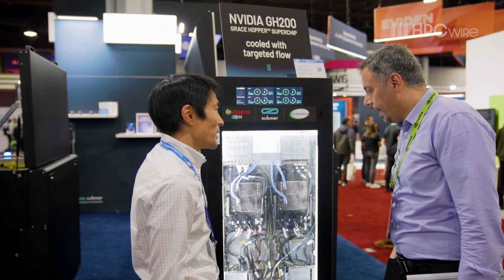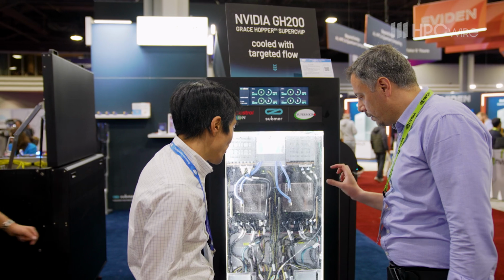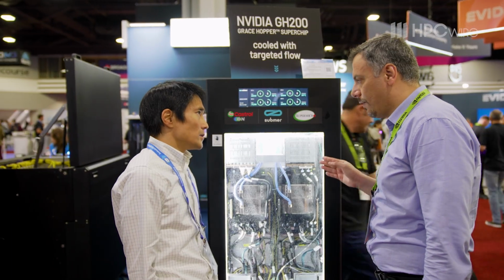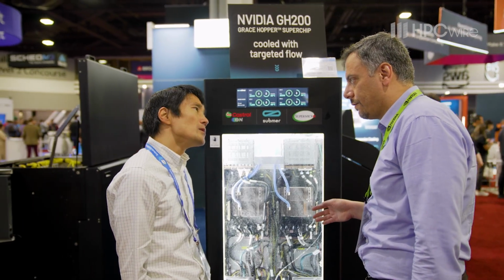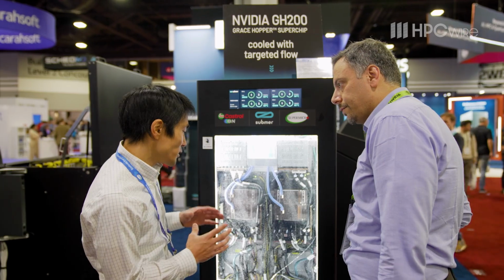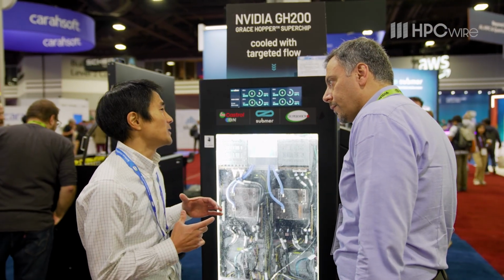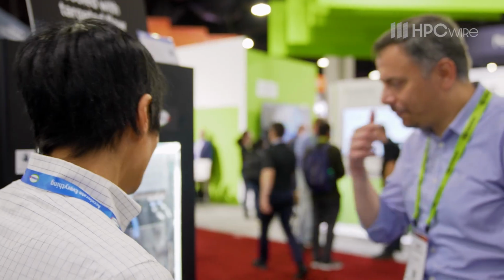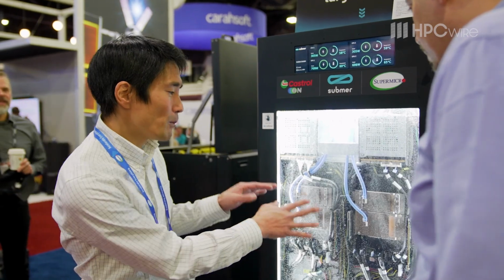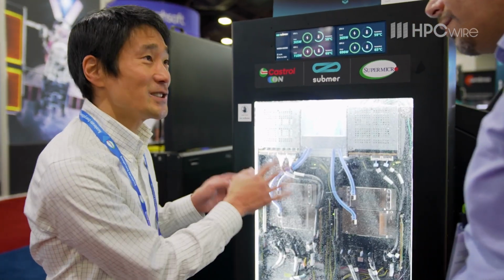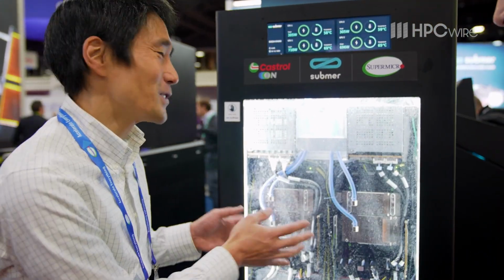With immersion cooling, it's not that way. There is no air cooling component. It's just one loop, and the power required for cooling is just the power required to power a couple of pumps and a couple of fans. That's how you get down to a PUE of 1.02. So with immersion cooling, you get the best of both worlds: high performance cooling, but you're saving a lot of money and energy in the process.